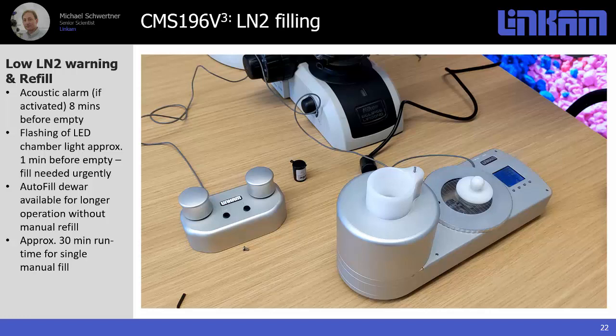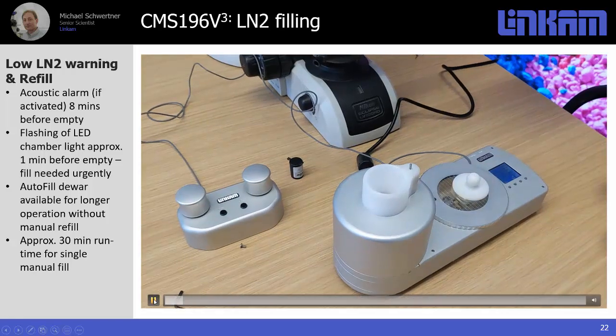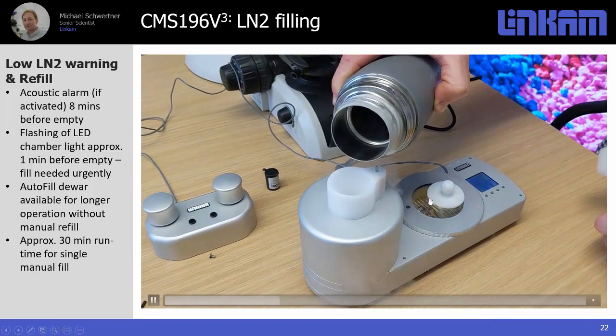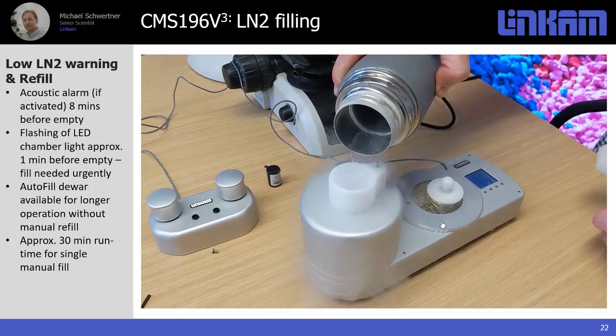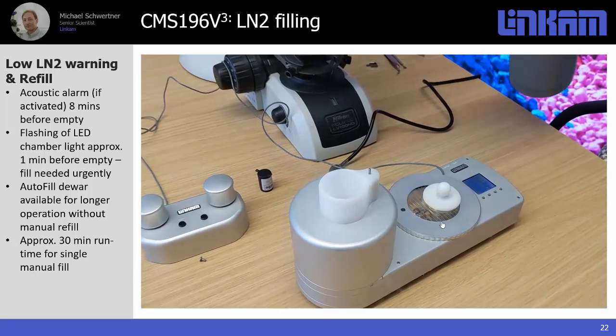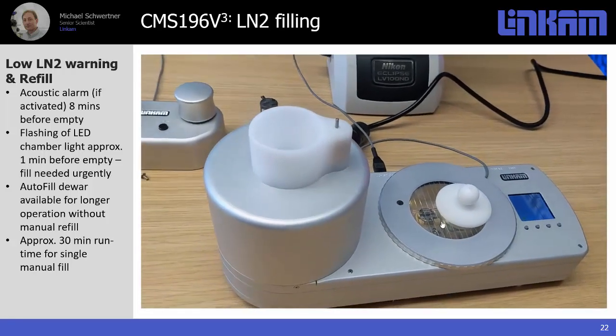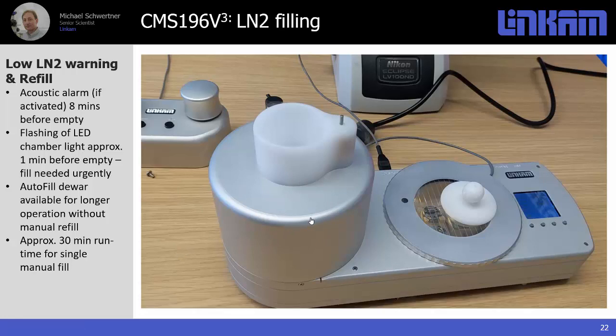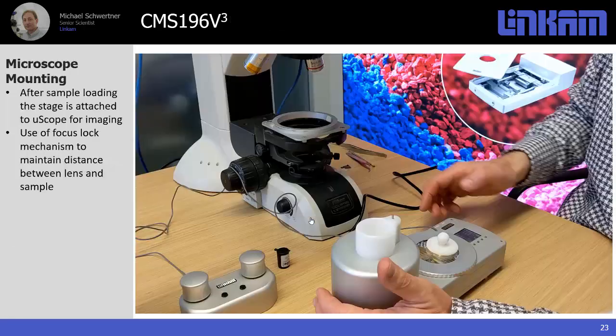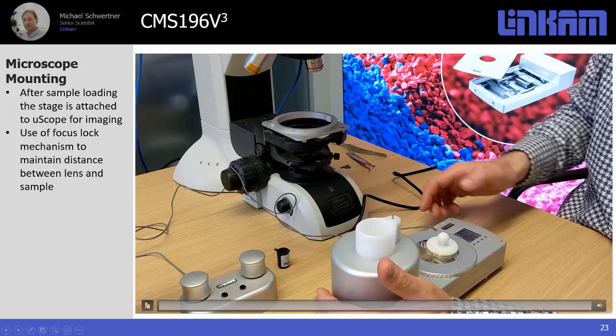Before continuing with microscope mounting, let's look at the alarms the stage will give. The optical alarm shows the chamber light flashing to remind you to refill liquid nitrogen; there is also a beeping alarm configurable in the menu. The stage lasts roughly half an hour with the internal dewar, or it can last half a day with a three-liter external dewar.